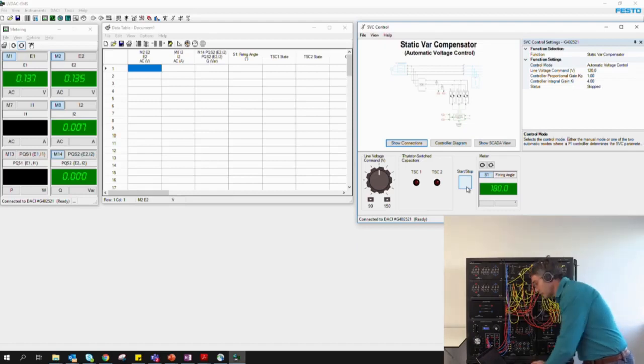I have pre-configured LVDAC here to display all the information I'm interested in: the two voltages at the source sending and receiving end, the current through the load, and the reactive power exchange between the SVC and the circuit. Our data table is also configured to record E2, I2, the reactive power, the firing angle sent to our thyristors to control the amount of reactive power they consume, and finally the state of our two TSCs, whether they are in or out of the circuit. The static VAR compensator control window is accessed through the DACI menu, under SVC control.